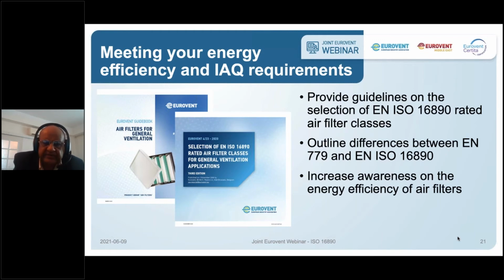Also, there's a point that comes to me time and again - during webinars or interviews, people ask if offices will go with HEPA filters very soon. Offices are not designed for HEPA filters; the airside systems are not designed for that, and they impose a lot of external static pressure. Changing systems to get into HEPA - if push comes to shove, we'll all have to do it - but that's not the first choice. First, stick to the HVAC filters.